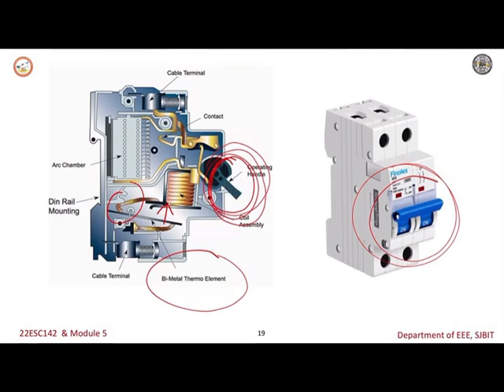The merit compared to your fuses is that it can easily identify the faulty zone when it is tripped. That's why I mentioned the branch MCBs. If we use multiple MCBs, whenever one trips, we can easily identify where the fault has occurred or where the overloading has occurred. That is one advantage.